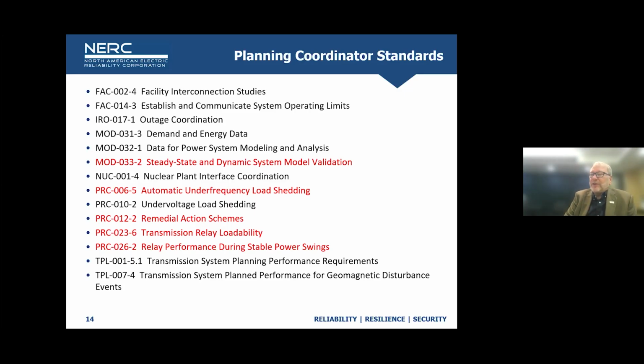Transmission relay loadability, they're required to specify what the relay loadability limits are for each one of the relays. And then they're also expected in PRC 26 to ensure that load responsive protective relays don't trip in response to stable power swings during non-fault conditions. So they've got a few more responsibilities in those areas.